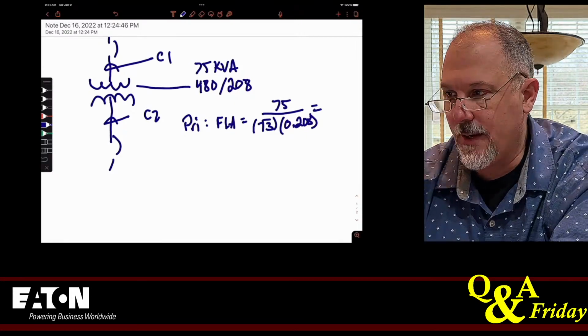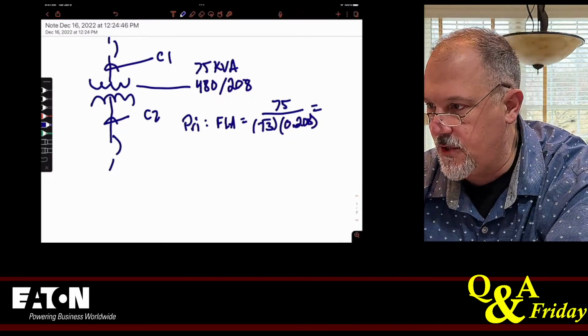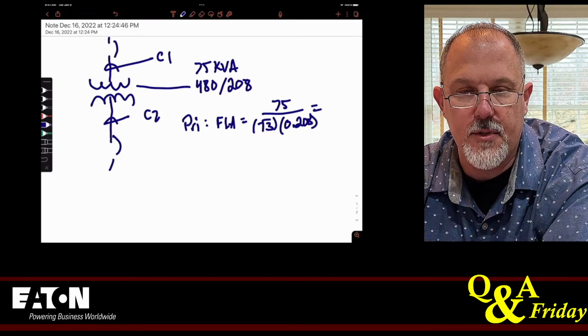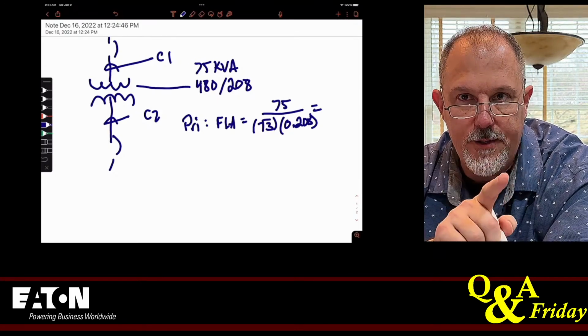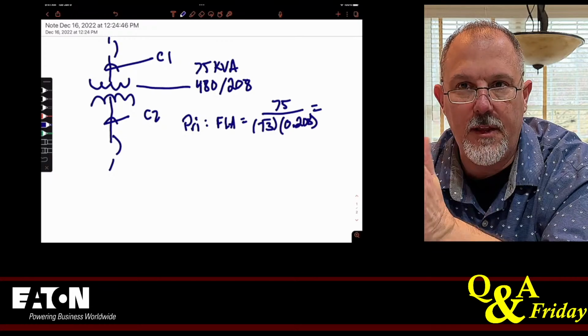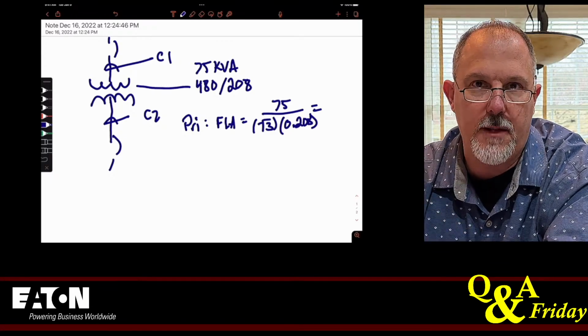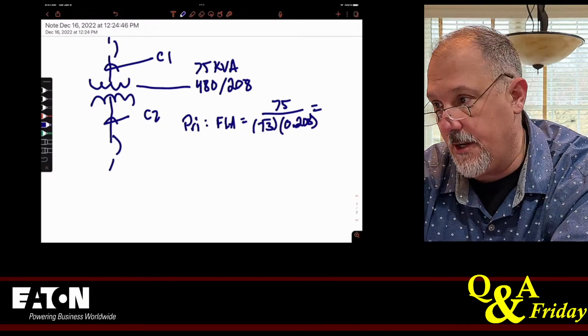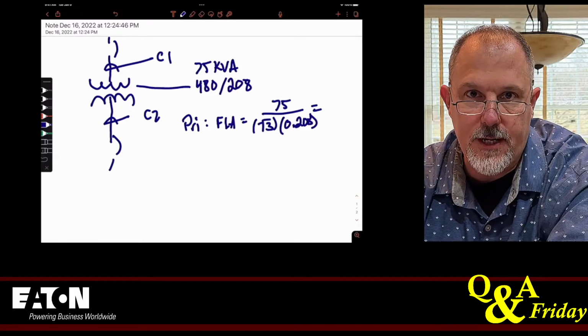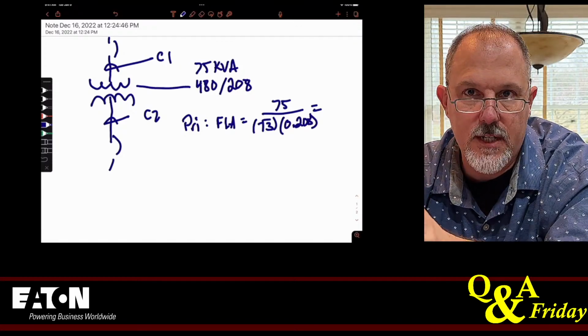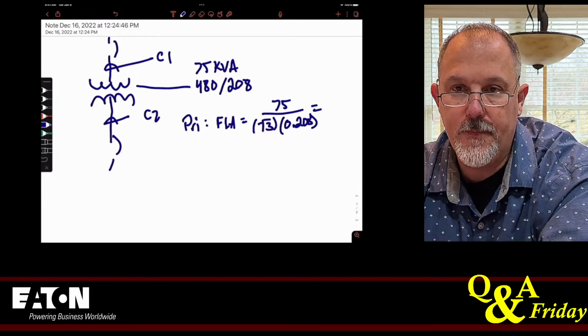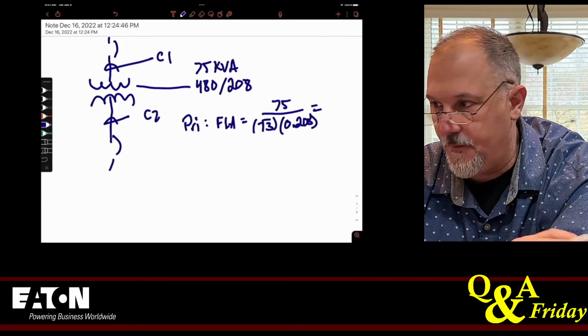All right, so we're back here. I've got a 75 kVA transformer, 480 to 208. I'm not going to worry about the percent impedance, because the only reason I would want to know the percent impedance is for available fault current on the secondary. So when I'm picking my primary and secondary overcurrent devices, outside of the interrupting ratings, I'm going to be starting with the full load amps.